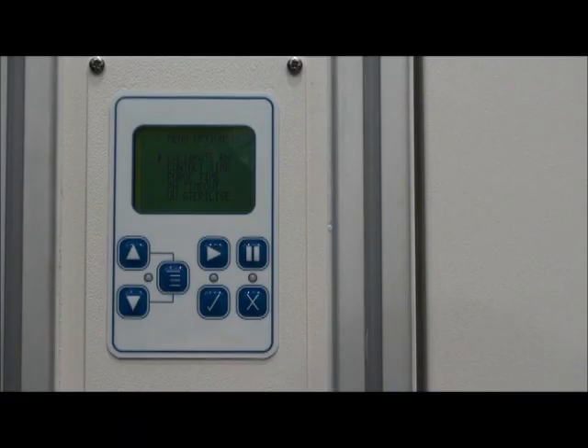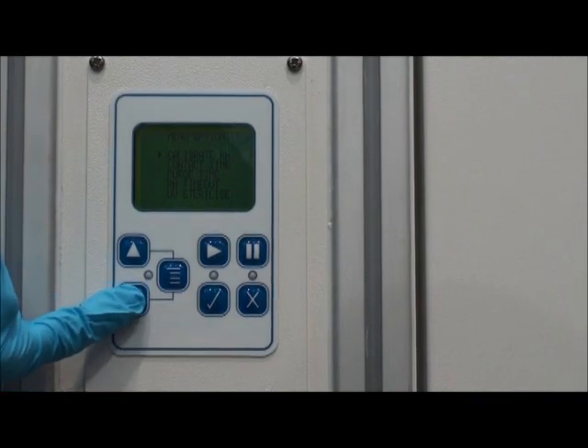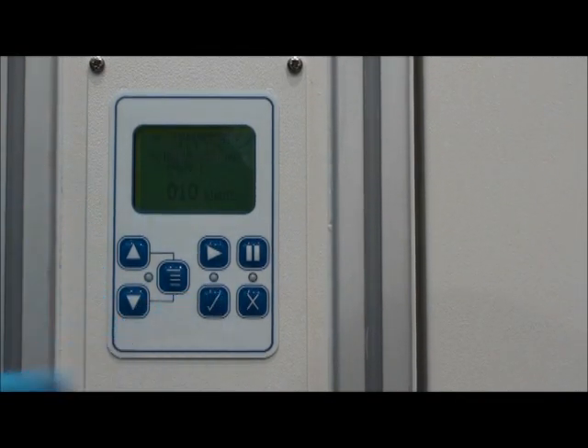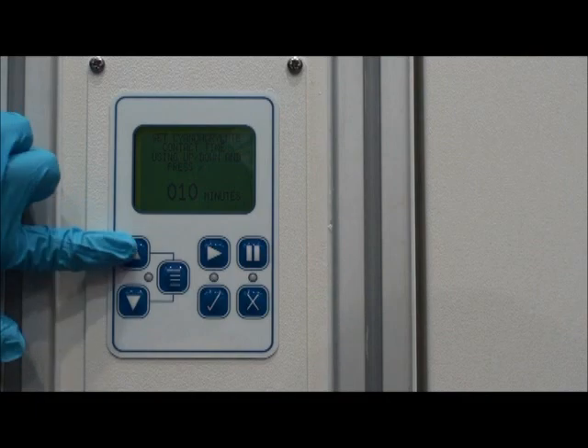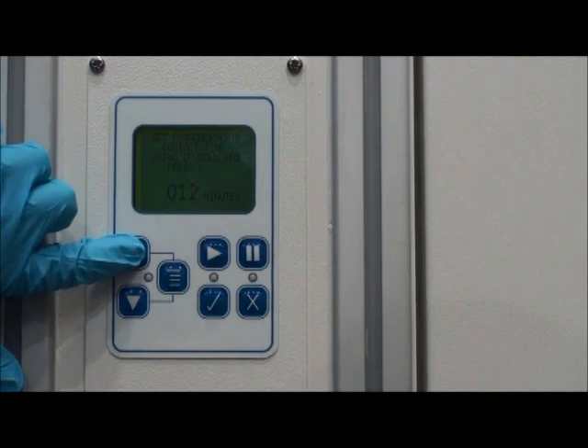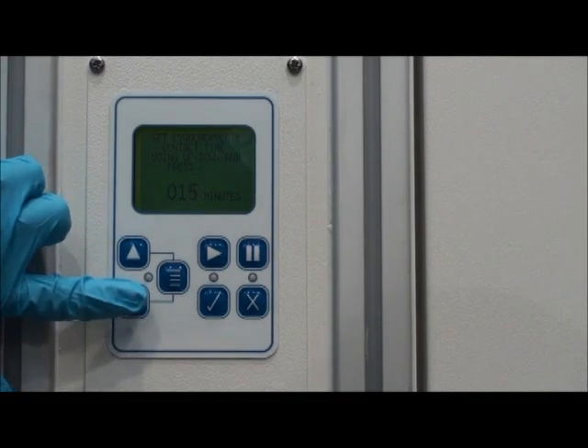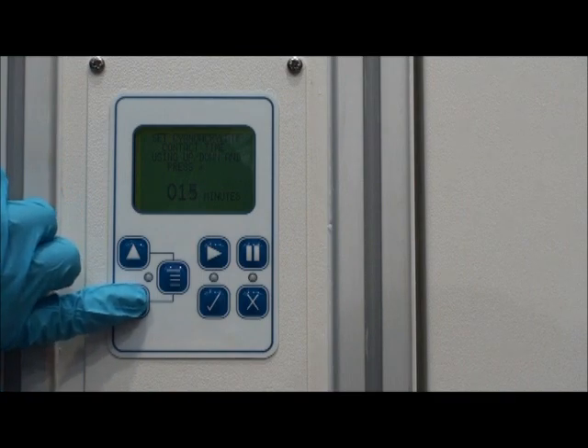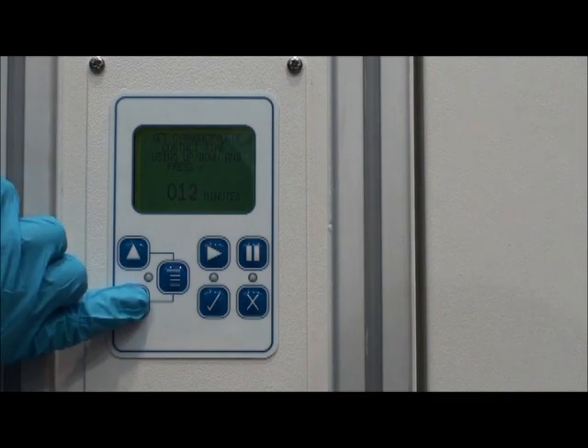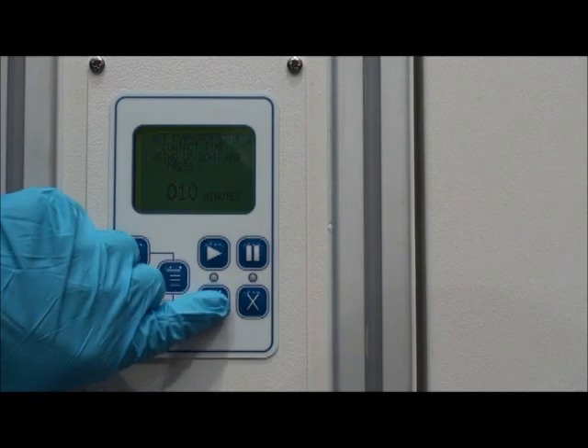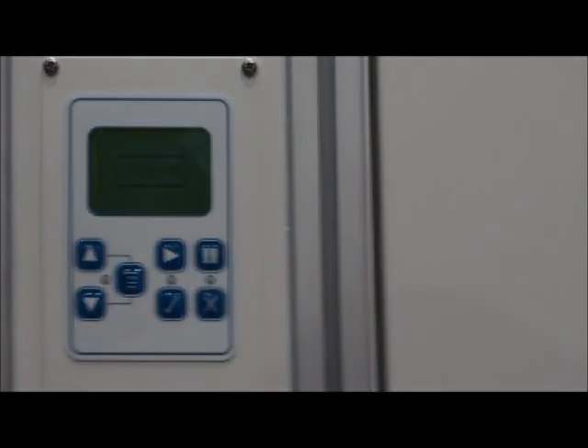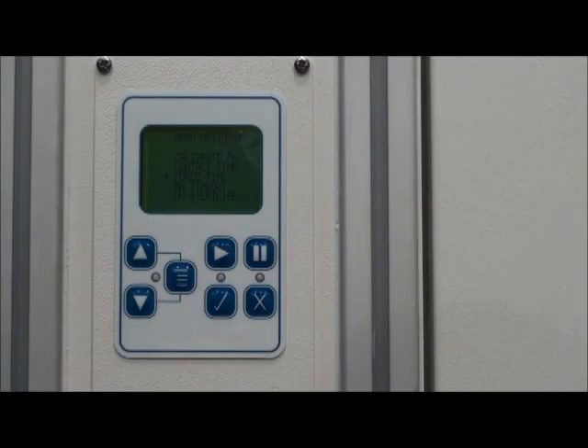Next on the menu is the contact time. Accepting that by pressing the tick. At the moment it's set for 10 minutes. You can press the up and down keys to display your desired setting upwards or downwards. And to accept, press the tick. Next on the menu is the purge time. This is the time it takes to extract the chamber on completion of the purging cycle.